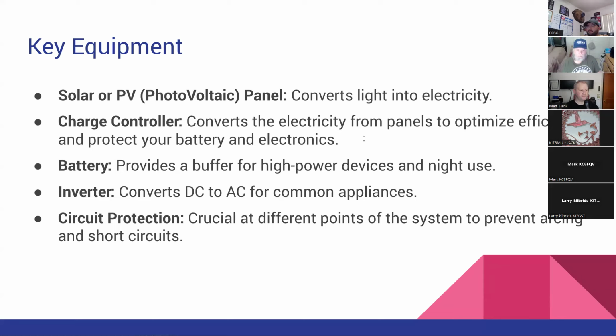Circuit protection's important - you want to have that at different points of your system. DC in particular arcs very easily. So if you're running a string of a few solar panels, you could be pushing 100 volts DC, and if there's current flowing when you disconnect it, you might create an arc. So it's good to have circuit breakers designed for that to extinguish the arc and prevent fires.